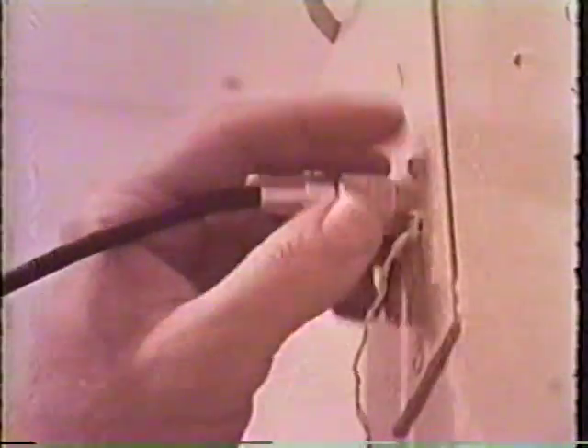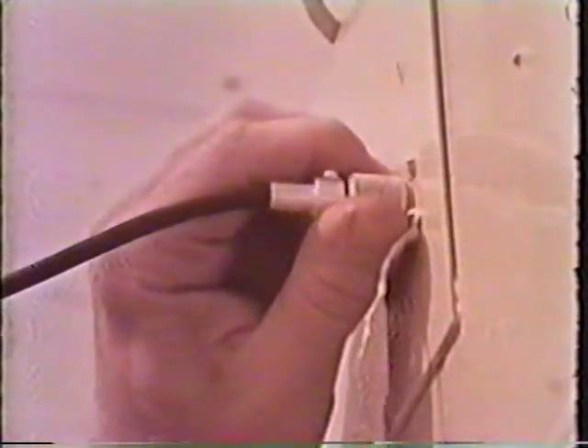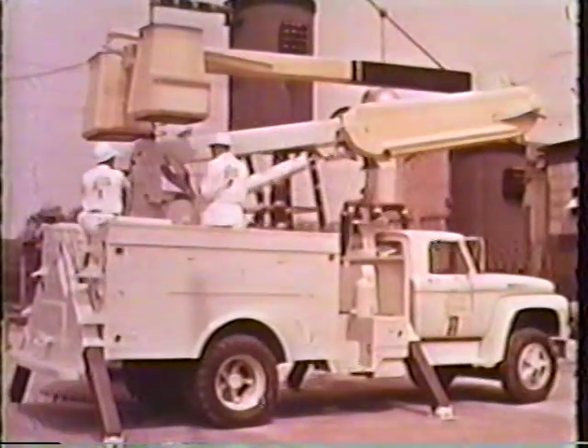In the Holland elbow, the inner surface of the fiberglass arm and all the control rods inside the arm are protected from contamination by a lifetime coating of silicone. Arm current measurements are an important part of the certification test received by every Holland live line elbow before delivery. A microammeter is plugged into the coaxial cable outlet on the lower arm to make the arm current readings.